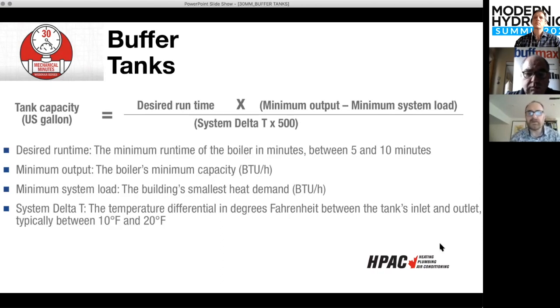We size it based on my desired runtime. I want to minimize short cycling in my boiler. I would say that the minimum runtime you should ever be looking for is 10 minutes. So when my boiler comes on in response to a call for heat, I want it to run at least 10 minutes before it shuts off. If it's running less than 10 minutes at a time, I'm going to call that short cycling. So desired runtime, and then you're going to look at the minimum output.